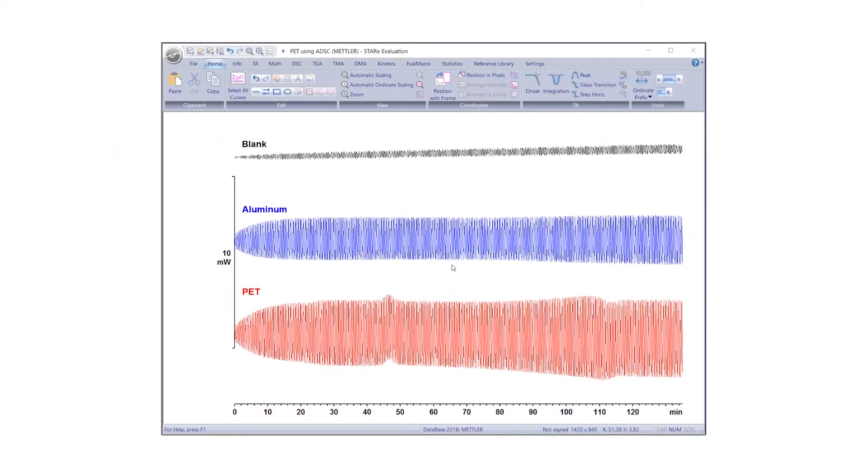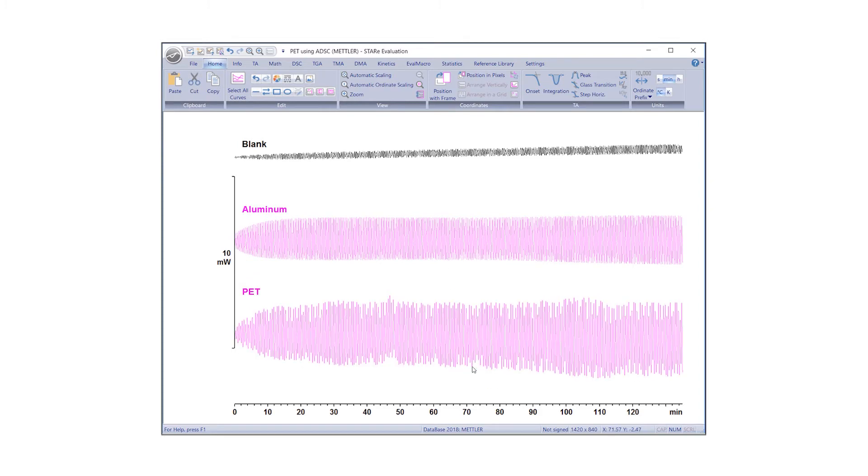Beginning with Step 1, perform the blank, reference and sample DSC measurements using the same method. Step 2, to compensate for drift, you will need to subtract the blank curve from the aluminum and PET curves. Hold down the Control key and left-click to select the aluminum curve, PET sample curve, and blank curve.